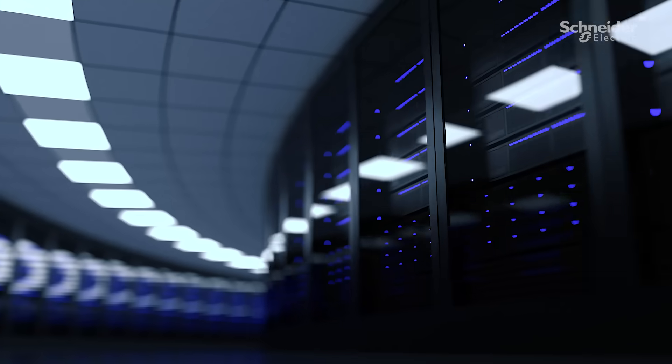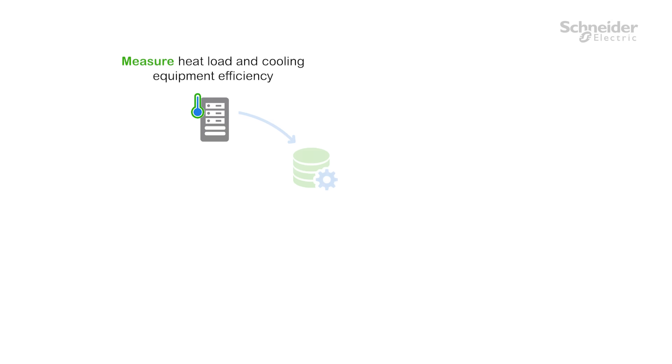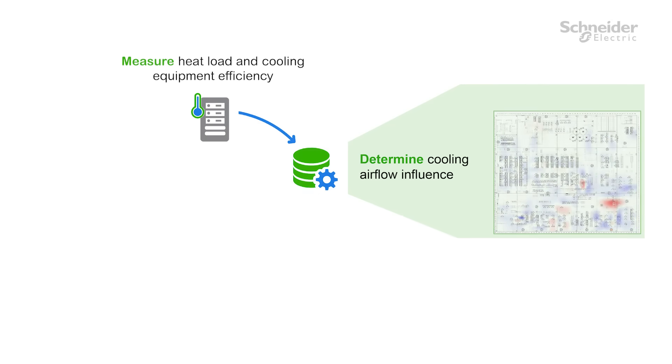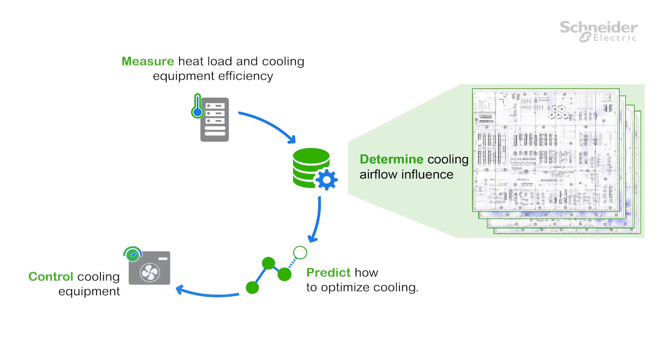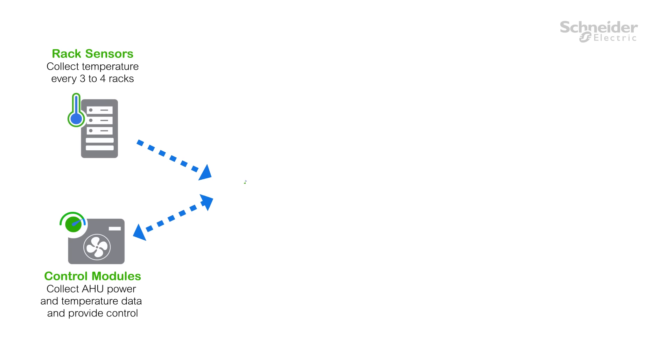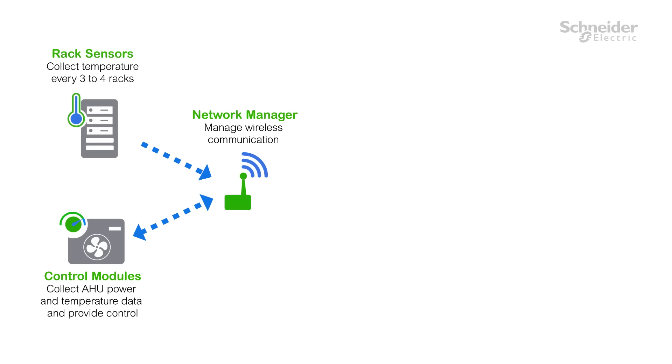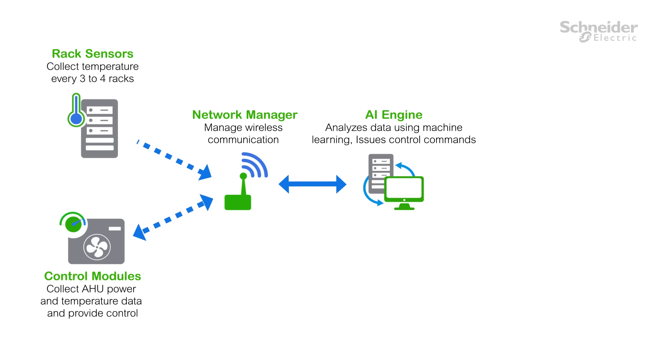Cooling Optimize is a closed-loop system. It reacts to real-time data, automatically identifies and eliminates hot spots, and helps diagnose potential facility risks. Our rack sensors and control modules collect temperature data every three to four racks, ensuring the right cooling is received at all points. The data is then fed to the AI engine through the network manager.